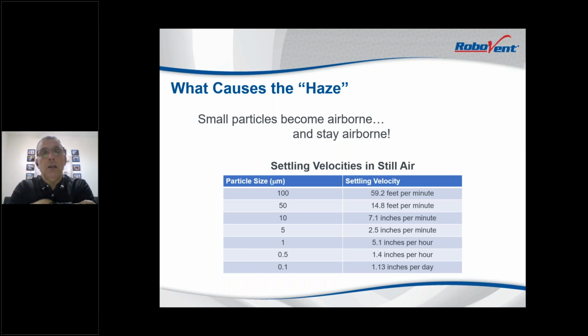So if you look at that chart, a 1 micron particle will settle at about 5 inches per hour. So in still air, that particle will only drop about 5 inches per hour. So these materials that we're talking about tend to stay airborne. And as you're generating these particulates, the concentration just continues to go up until you either evacuate the zone with filtration or HVAC systems, or you capture it local to the machine and then filter it.